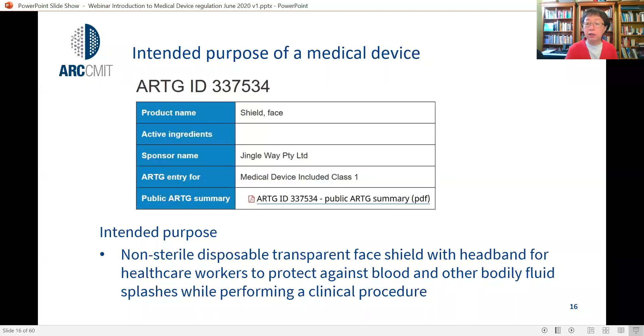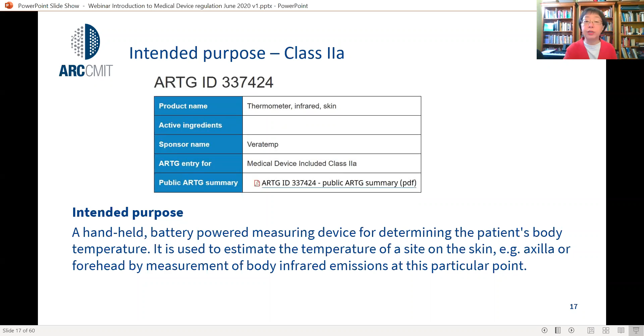Similarly, as we move up the risk profile for a class 2 device, the thermometer that is hand carried and battery powered, supplied by a sponsor called Veratemp, again, if you go to that public ARTG summary, the intended purpose says handheld battery-powered measuring device for determining the patient's body temperature. It is used to estimate the temperature of a site on the skin, such as the axilla or forehead, by measurement of a body infrared emission at this particular point. So you can see that for class 2A, there is a power source, and it's measuring the body infrared emissions.